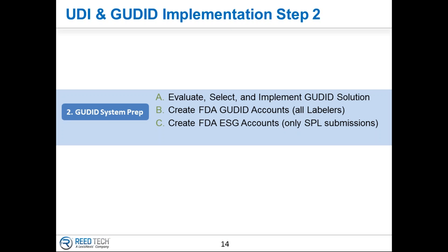The FDA technically calls this scenario a misbranding. Some companies, if they are extremely cautious, will stop production of that product. You obviously want to rectify that as soon as possible. We have not heard of any fines levied or imprisonments or civil activities that the FDA has levied against a company. So I believe there's going to be some leniency in getting started. It would be best to identify those products and have some type of plan in the event the FDA comes on site.